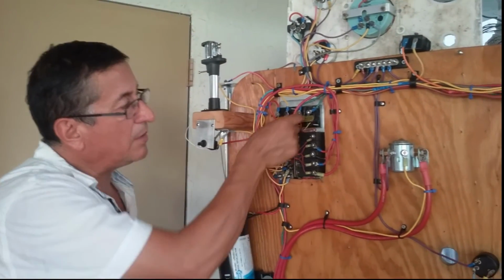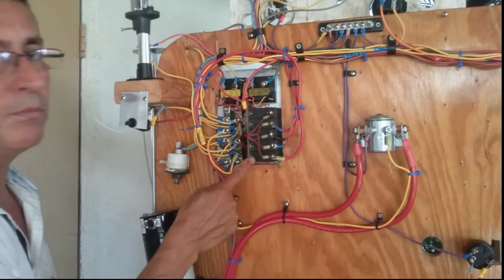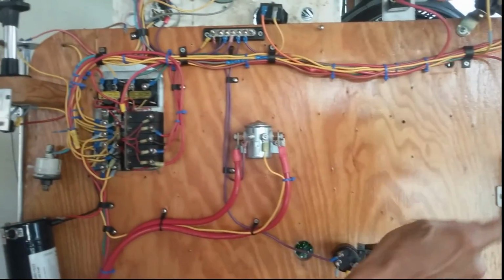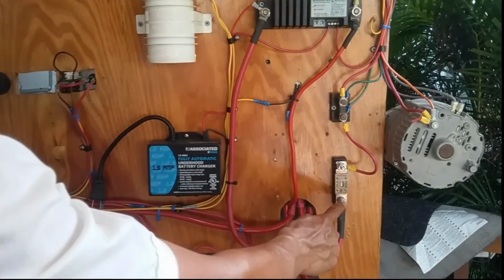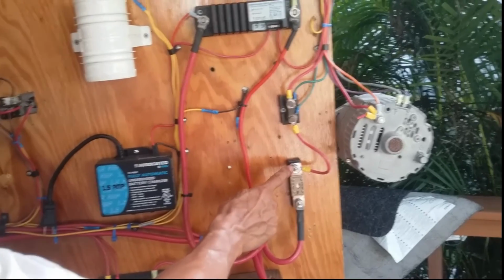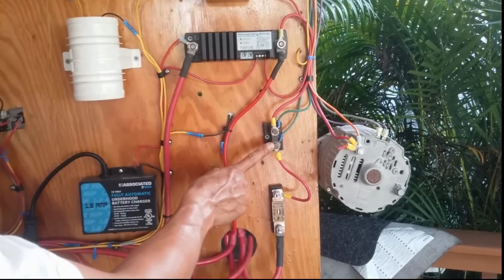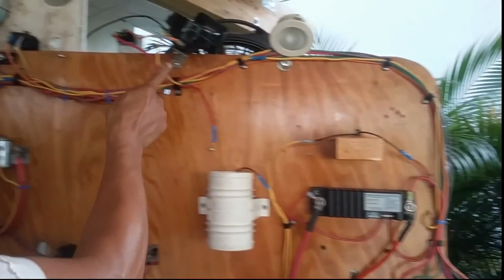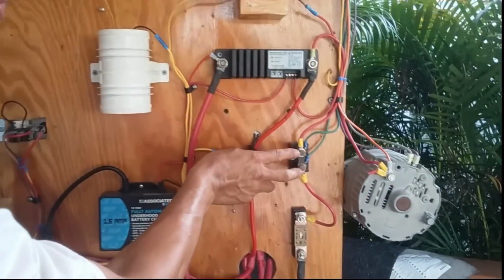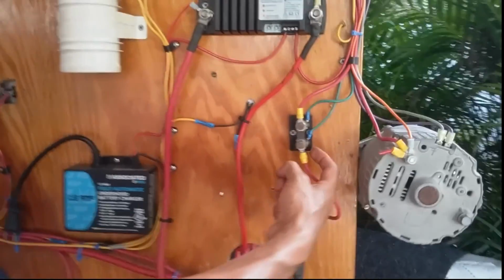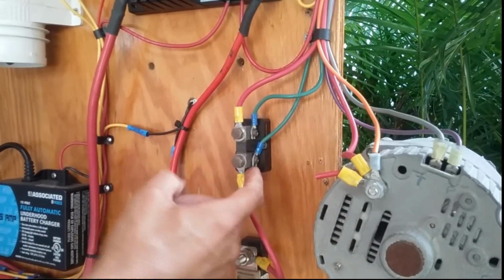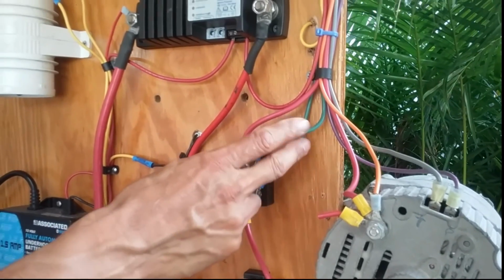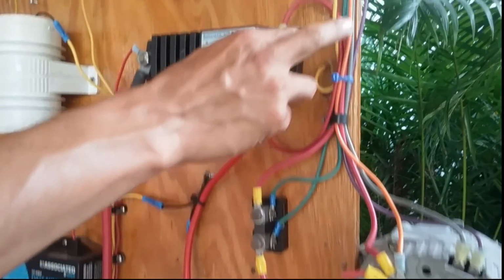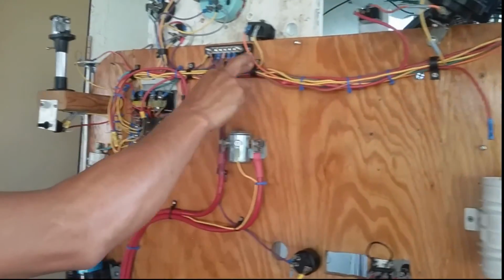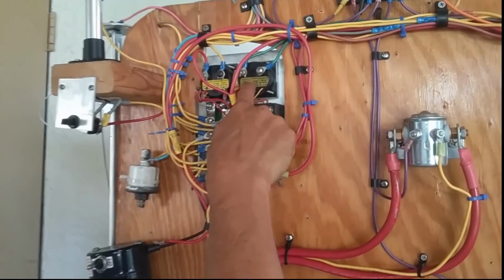Okay, this is the positive cable in order to feed the positive bus bar. That positive cable is coming from the switch selector, the battery switch selector. That's the power from the battery switch selector entering the fuse. In the output of the fuse, the power enters the shunt, and the power continues into the positive bus bar. Okay, in one side of the shunt, you have two small terminals where you connect the small wires, those green wires. And those green wires enter here into the terminals of the ammeter.